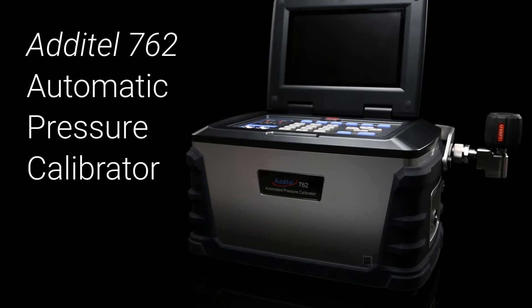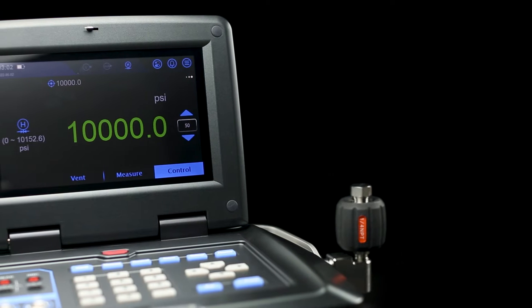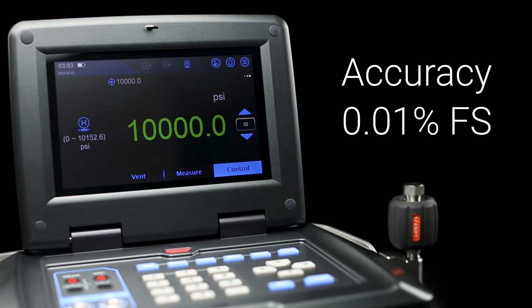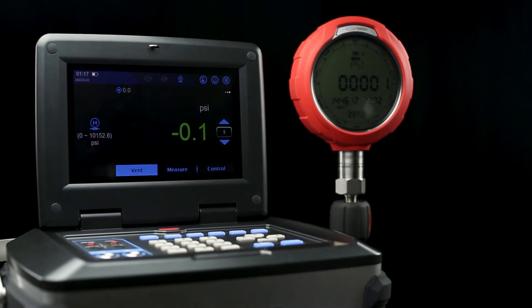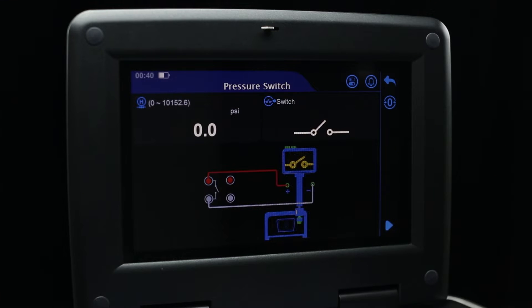The Additel 762 is one of the fastest automatic pressure calibrators on the market, with a range up to 10,000 PSI and an accuracy up to 0.01% full span. In this video, we'll show you how to easily set up a task function to calibrate your pressure devices, allowing you to build a task library for efficient testing and data management.